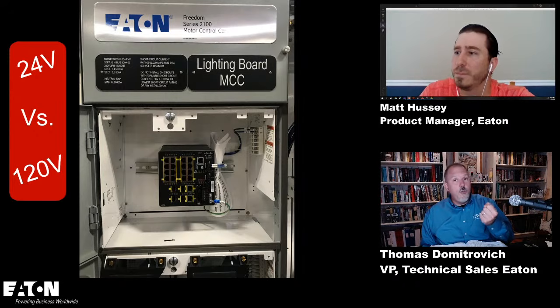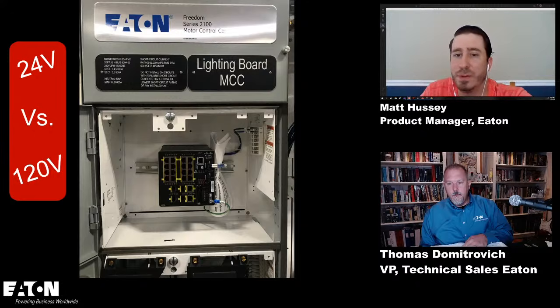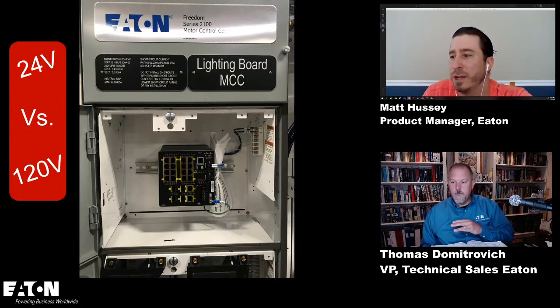So would you be running 600 volt rated wire inside there for communications? You would. The communications cabling you'll find has a similar capability. It'll have 600 volt, AWM rating, so it's intended to be integral to the manufacturer supplied equipment. So we're not looking at it from an installation standpoint because it's integral to the assembly. We do provide 600 volt rated communications cabling. There's a pretty good pictograph, I think Belden does, to define the differences between 600 volt type tray cable, maybe like a UL 1277, versus 600 volt AWM cabling.